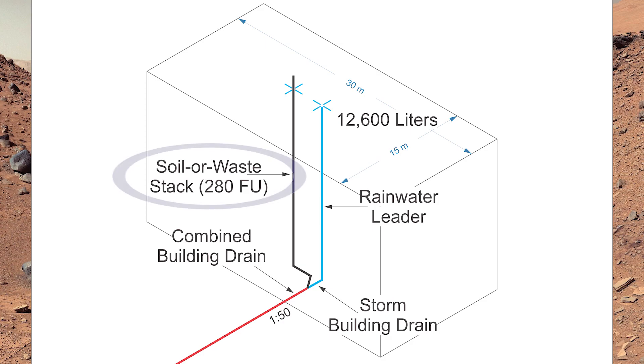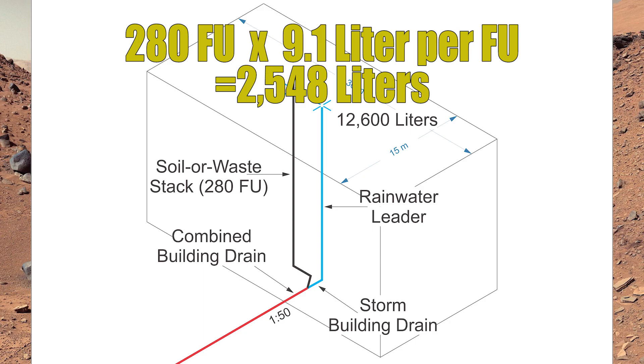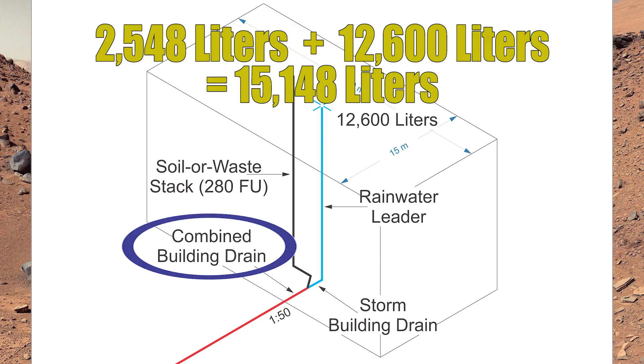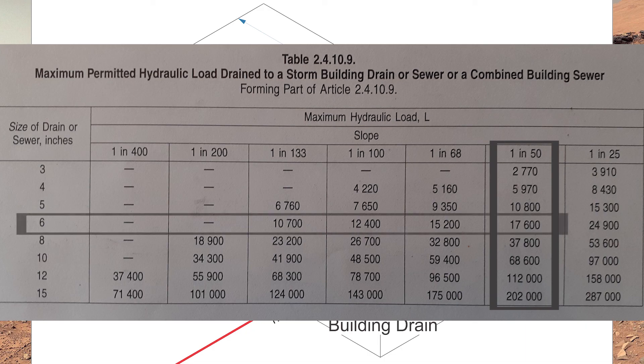This second example is exactly like the last one, except now we have 280 fixture units draining down that soil-or-waste stack. Remembering the code clause: if you have more than 260 fixture units, you take that fixture unit value and multiply it by 9.1 liters per fixture unit. So: 280 fixture units times 9.1 equals 2,548 liters. To size the combined building drain, I take that 2,548 liters and add it to the rainwater load of 12,600 liters, giving 15,148 liters. Back into table 2410.9, still grading at 1 in 50 — six inch is still good for the combined building sewer.